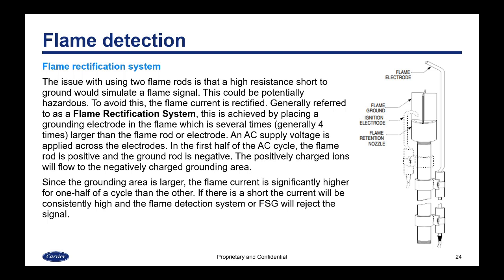To avoid this, the flame current is rectified. Generally referred to as a flame rectification system, this is achieved by placing a grounding electrode in the flame that is several times — generally four times — larger than the flame rod or electrode. An AC supply voltage is applied across the electrodes. In the first half cycle of AC, the flame rod is positive and the ground rod is negative. The positively charged ions will flow into the negatively charged grounding area. Since the grounding area is larger, the flame current is significantly higher for one half of a cycle than the other. If there is a short, the current will be consistently high and the flame detection system will reject the signal.